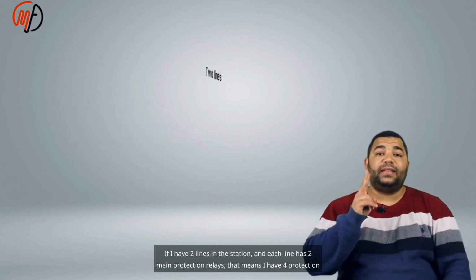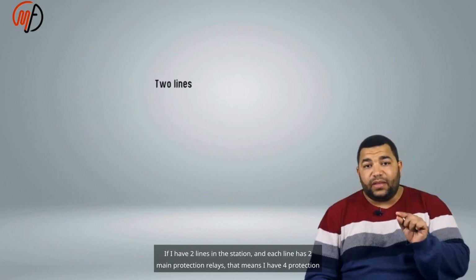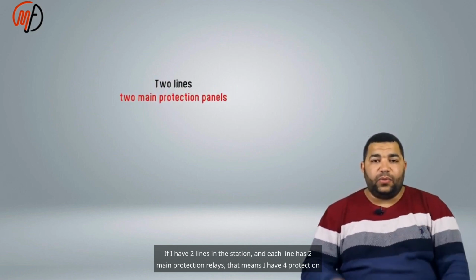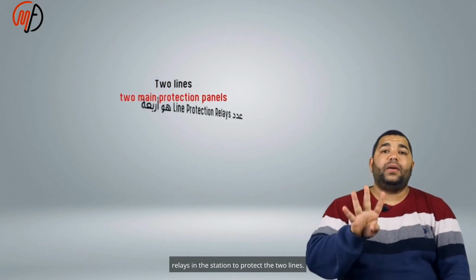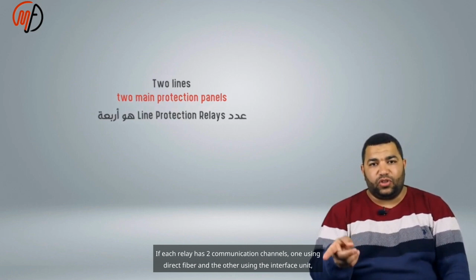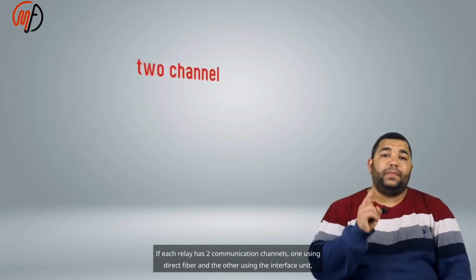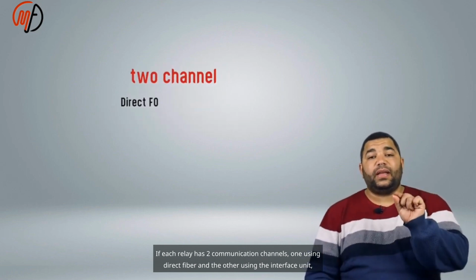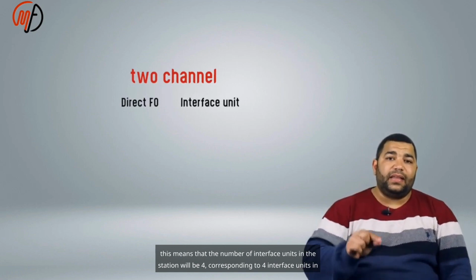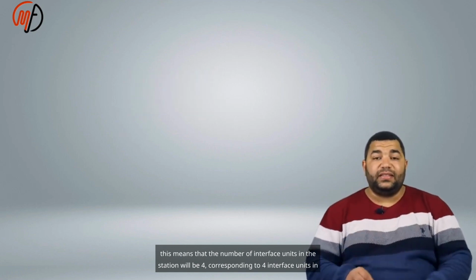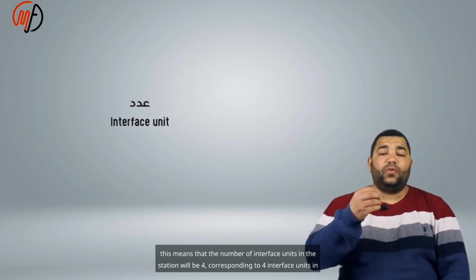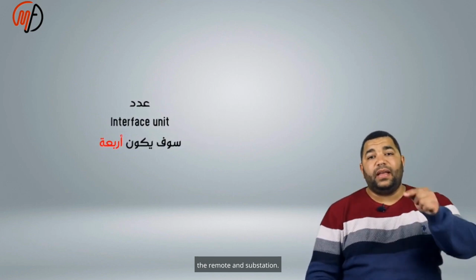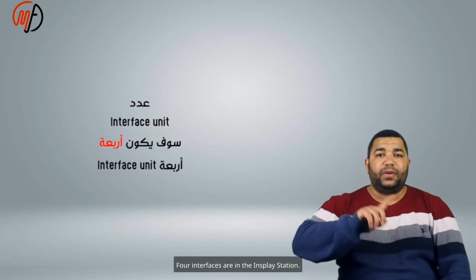If I have 2 lines in the station and each line has 2 main protection relays, that means I have 4 protection relays in the station to protect the 2 lines. If each relay has 2 communication channels, one using direct fiber and the other using the interface unit, this means that the number of interface units in the station will be 4, corresponding to 4 interface units in the remote substation. 4 interfaces are in the in-place station.